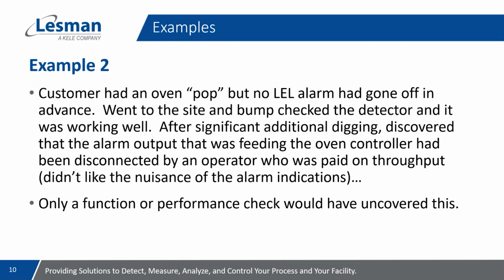So I went to the detector and did a bump check. Everything looked great, still right on the button. Continuing to dig, I did a system check where I put gas on the sensor to check the outputs. Again, everything looked great from the sensor side. Eventually, after more digging, we discovered that the sensor input to the oven controller had been defeated. My sensor had been screaming high gas, but the receiving system was not listening. Somebody had decided that the alarm was annoying and was impacting production rates. The good news was that nobody was physically injured, although a couple people ended up losing their jobs. A standard bump check or calibration, since the outputs get isolated in these new technology transmitters, would never have uncovered the situation. Only a performance check would have been able to test and expose that.